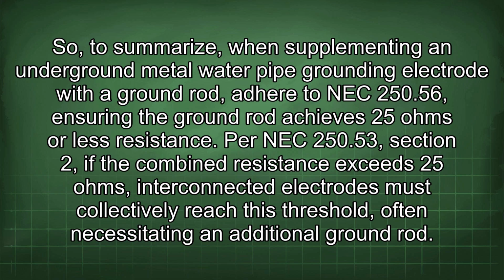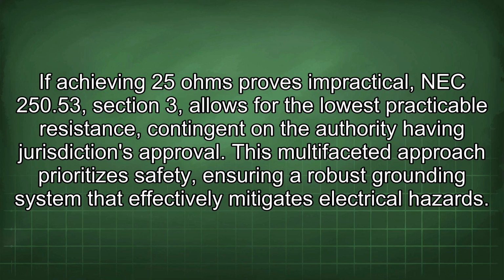So, to summarize, when supplementing an underground metal water pipe grounding electrode with a ground rod, adhere to NEC 250.56, ensuring the ground rod achieves 25 ohms or less resistance. Per NEC 250.53, Section 2, if the combined resistance exceeds 25 ohms, interconnected electrodes must collectively reach this threshold, often necessitating an additional ground rod. If achieving 25 ohms proves impractical, NEC 250.53, Section 3, allows for the lowest practicable resistance, contingent on the authority having jurisdiction's approval. This multifaceted approach prioritizes safety, ensuring a robust grounding system that effectively mitigates electrical hazards.